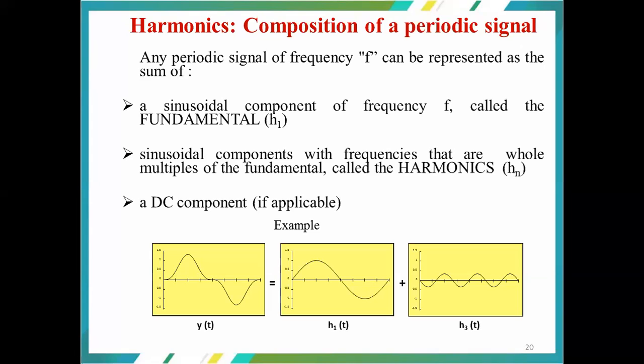Likewise, the fifth order harmonic component passes 5 cycles, whereas the seventh order harmonic component passes 7 cycles. So we are all aware that the amplitude and the shape of this current waveform is going to be the cause for the generation of the fluxes in the coils, and thereby we are going to have effects in the field system when you are supplying the motors or any other sensitive equipment with these harmonic components.